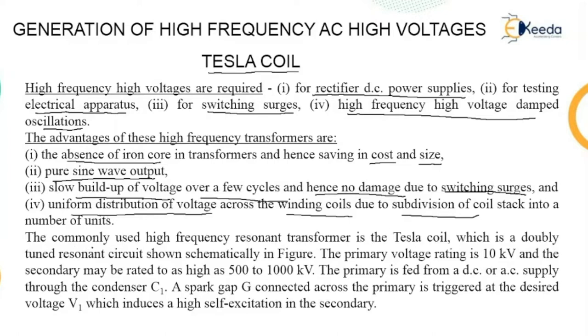The commonly used high frequency resonant transformer is the Tesla coil. The Tesla coil is generally used for the generation of high frequency high voltage, and it is a doubly tuned resonant circuit which is shown in the diagram on the next slide. The primary voltage rating is 10 kilovolt, and the secondary may be rated up to as high as 500 to 1000 kilovolt. The primary is fed either from AC or DC supply, using certain elements like capacitors and inductors.